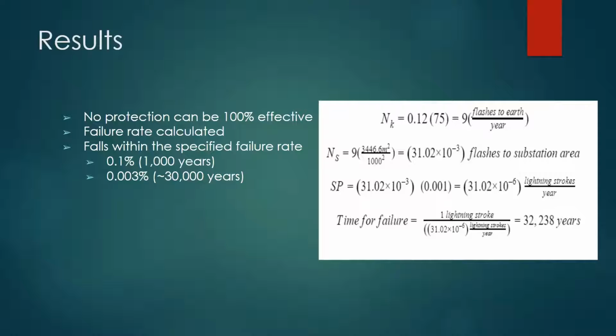And then we used that number and multiplied it by our desired failure rate, and we had a failure rate where one lightning stroke would get through every 32,000 years or so. So we wanted it to be a 0.1% chance of failure. We actually had a 0.003% chance of failure.